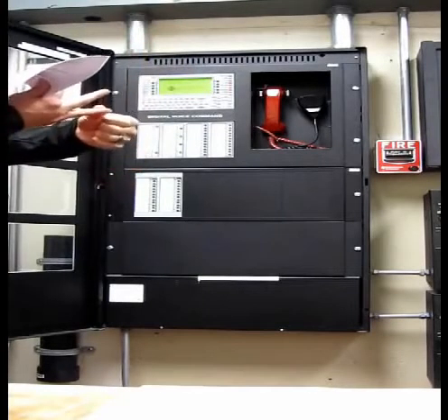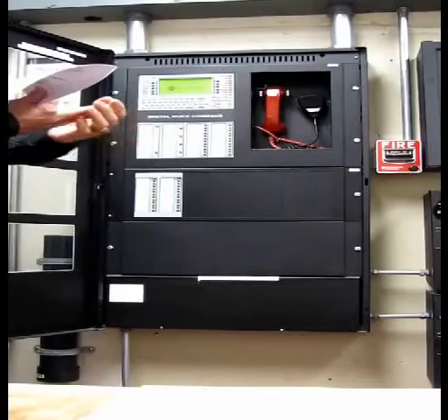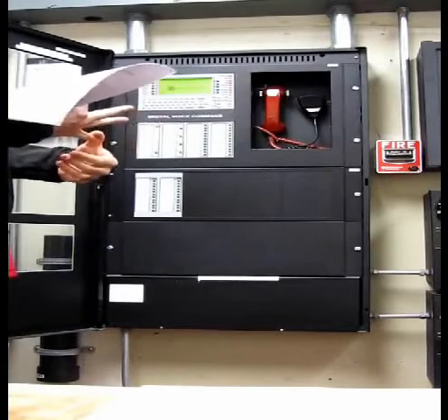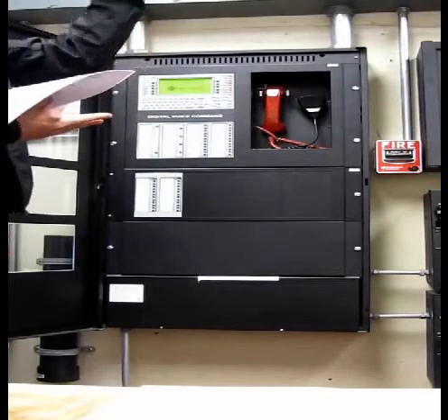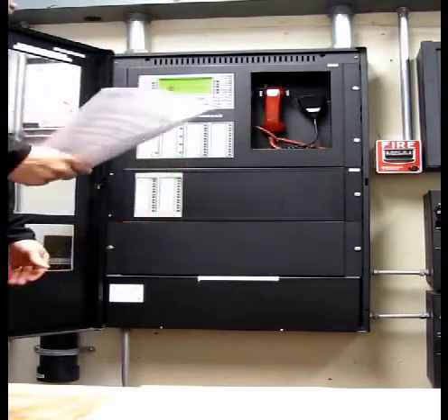So if you have a smoke detector on the third floor, it's not going to evacuate the whole building. It's going to go on third, second, and fourth. Just so you guys understand that one. So if you're on the first floor, you're only going to get 1 and 2. If you're on the 7th, you're going to get 7 and 6. So there's no floor above 7, there's no floor below 1.